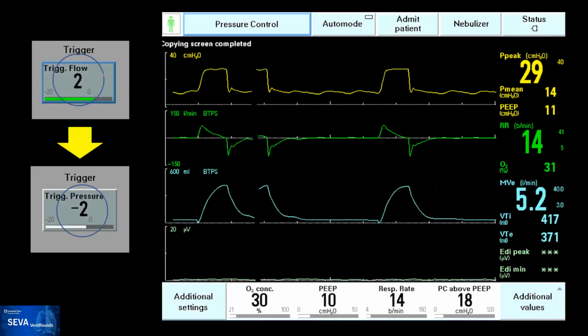So they changed the trigger from flow that was set at 2, and they changed it to a trigger of -2. And what you realize immediately is that there are these oscillations occurring here. And I wish Troy was here to tell us what was the heart rate for this patient. But you can see now the oscillations. None of the breaths are being triggered by the patient. And the rate is 14, which is meeting the same rate that you set. And there is no evidence of electrical activity of the diaphragm.